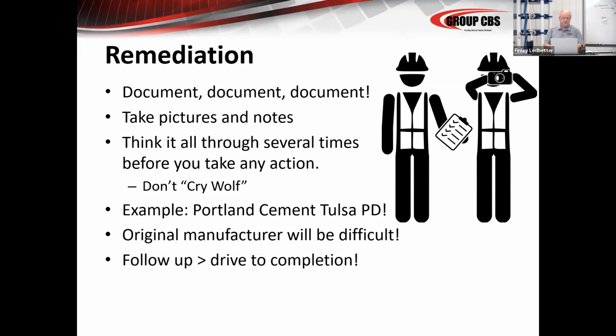That's when you say something, because the Portland Cement, Tulsa PD example is an example where I cried wolf immediately when I found some failed cables. And it turned out it was a problem that I had generated. The maintenance manager had already gone upstairs with it. They were already considering remediation, and I had made a mistake. So I'm just telling you, it's a very bad feeling when you do that, and it doesn't show good credibility. So be very careful in the future, everybody. Be careful in the future. Don't cry wolf until you're absolutely sure there's a wolf that you've actually seen.